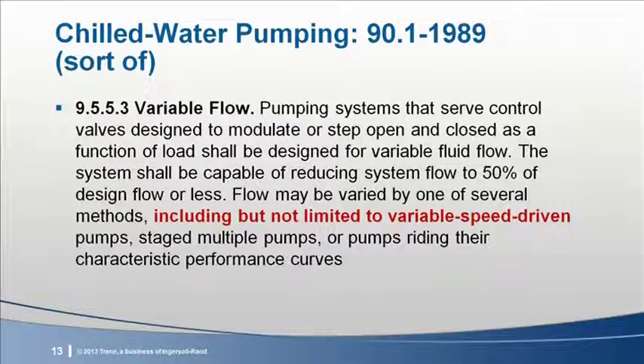Now, when I began working in the industry in 1982, VFDs on chilled water pumps were being applied to the secondary pumps in primary, secondary, or decoupled systems. 90.1 1989 required variable chilled water flow in some systems, but only mentioned variable speed drive pumps as an option to respond to the variable flow requirement.